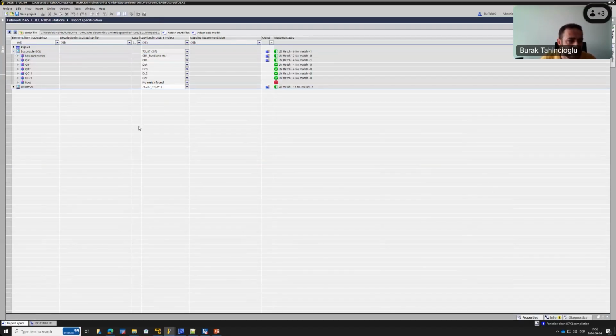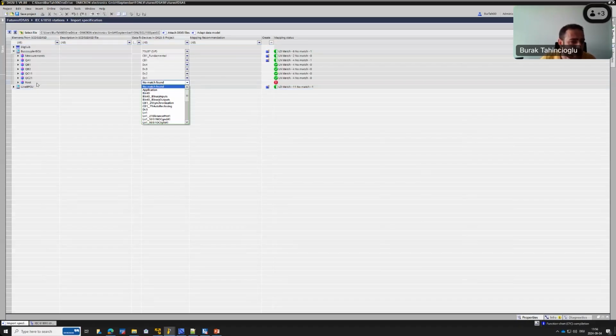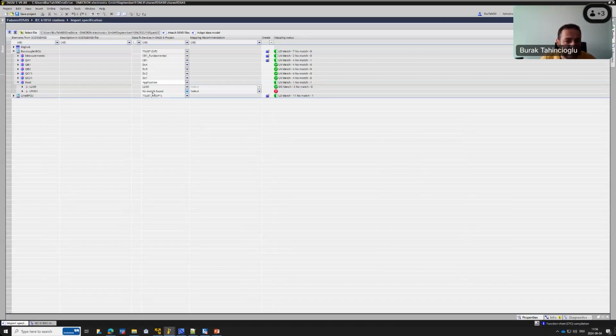This algorithm in DIGSI works automatically to try to match my logical devices with the data model. If there's no match, it informs me, and I try to find another logical device—for instance, root. Remember, root was the logical device which consists of the LPHD. You need some Siemens protection knowledge here: you know the application logical device corresponds to this one because under it there's an LPHD logical node which couldn't be found, but I know it's there.